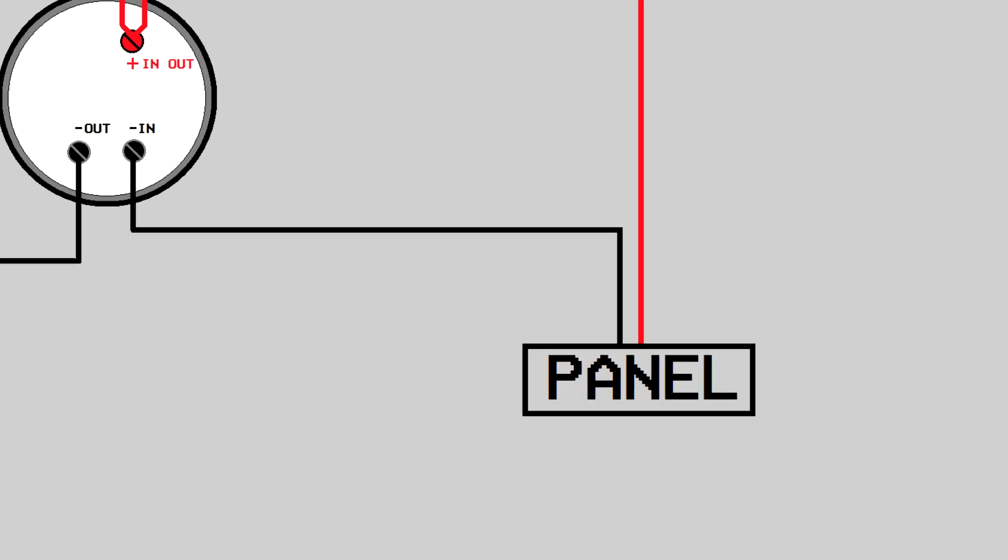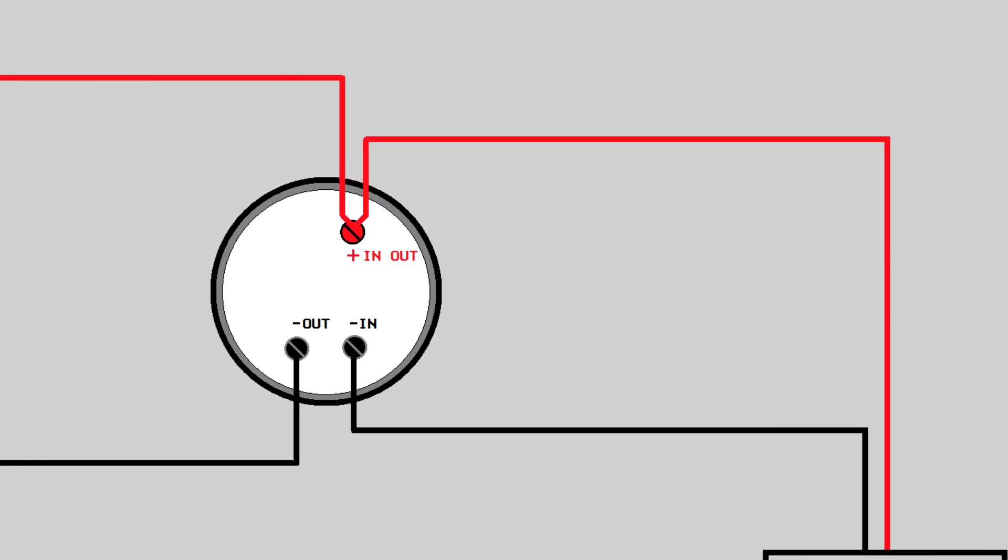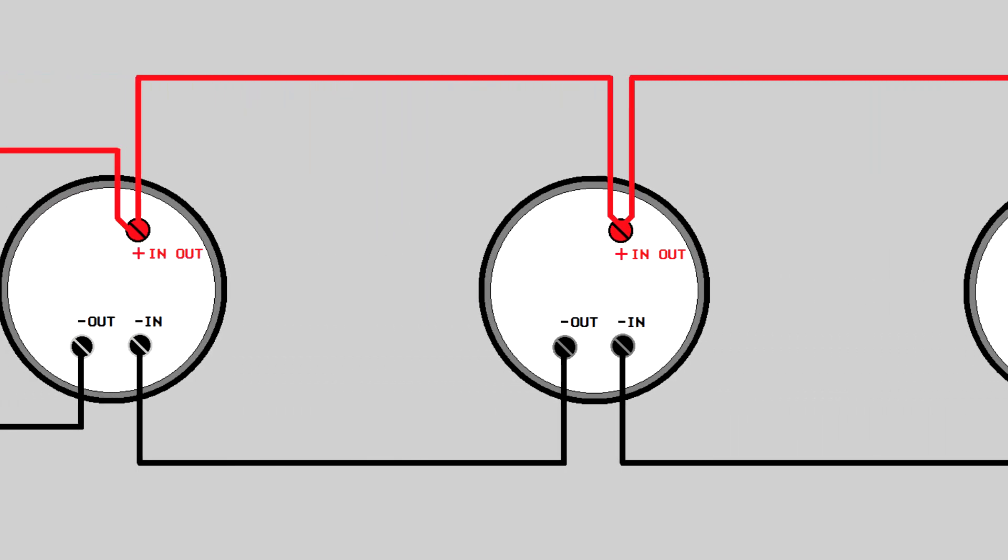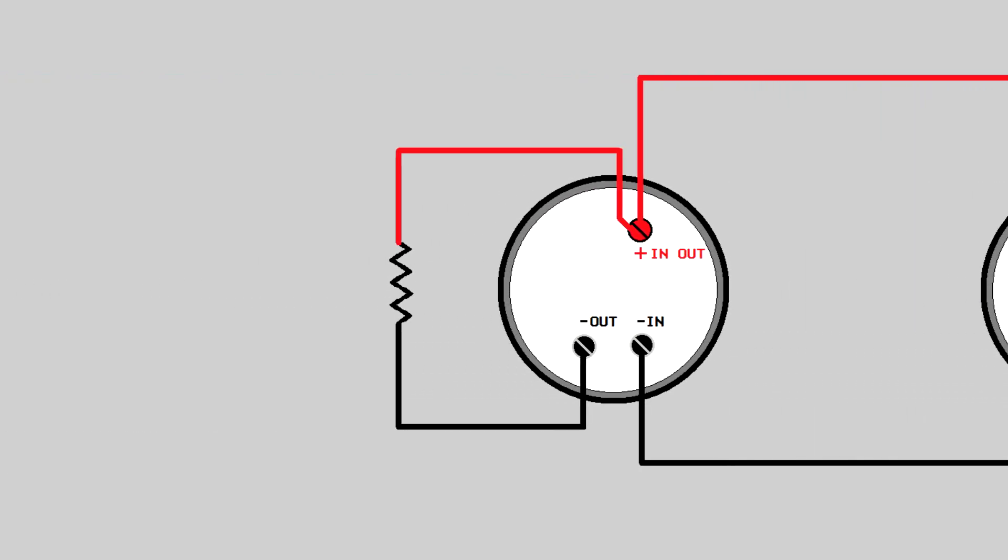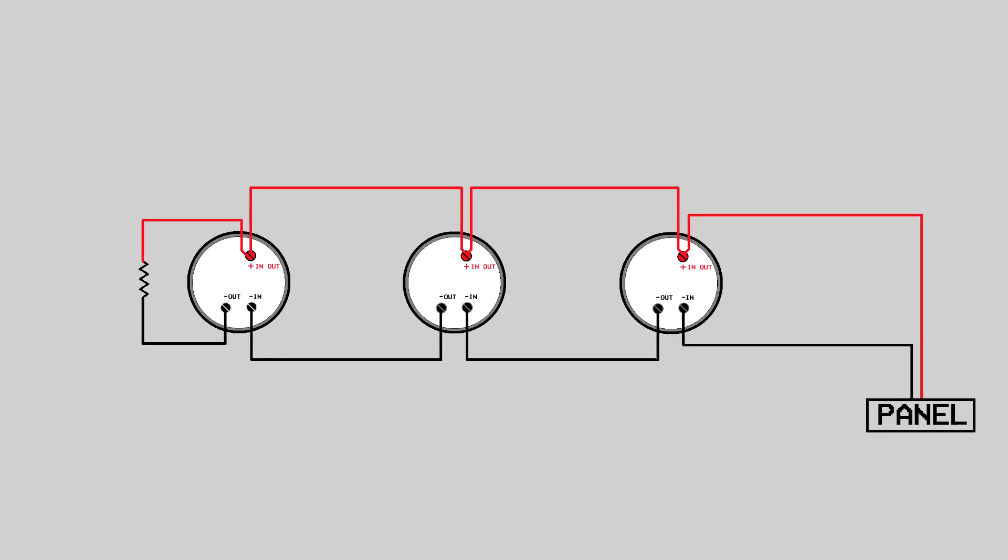The incoming negative wire from the panel will be connected to the terminal labeled negative in. The wire going to the next detector in the line will be connected to the negative out terminal. This is done for a fail safe mechanism. Let me explain that in detail.